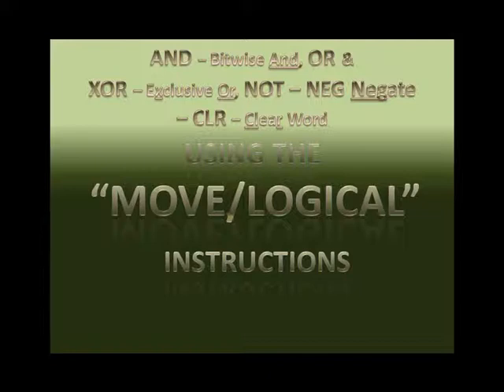Now the NOT and the NEGATE — people get those mixed up. The NEGATE instruction is the one you would most normally think of. If you put in a value of 6 and execute a NEGATE, you get negative 6. If you put in negative 6, you get 6. It just changes the sign. Whereas the NOT instruction goes through bit by bit and changes all the 1s to 0s and all the 0s to 1s.